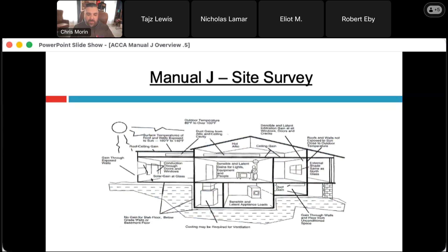So we talked quickly about the impacts on heat loss, which were very simple: temperature difference and construction quality, right? But when we look at heat gain, we actually have to take into account a lot of other things in the calculation, including the direction of glass and what's putting off heat inside the home. It's a much more complex calculation, which requires Manual J version 8 software. It's approved by ACCA. So the thing that impacts the heat gain the most is your windows, your fenestration.